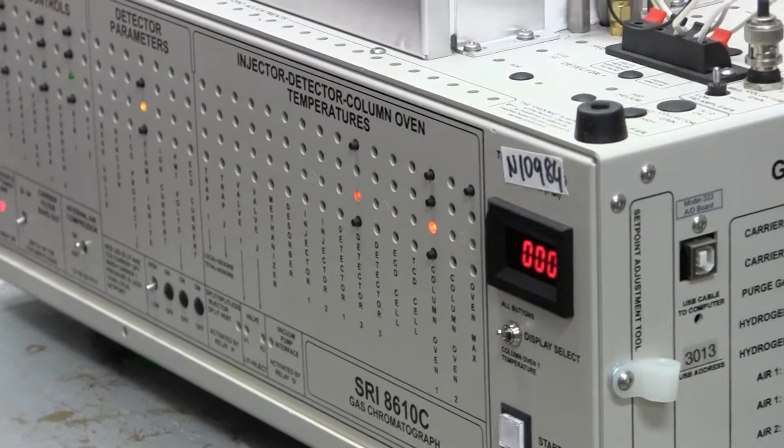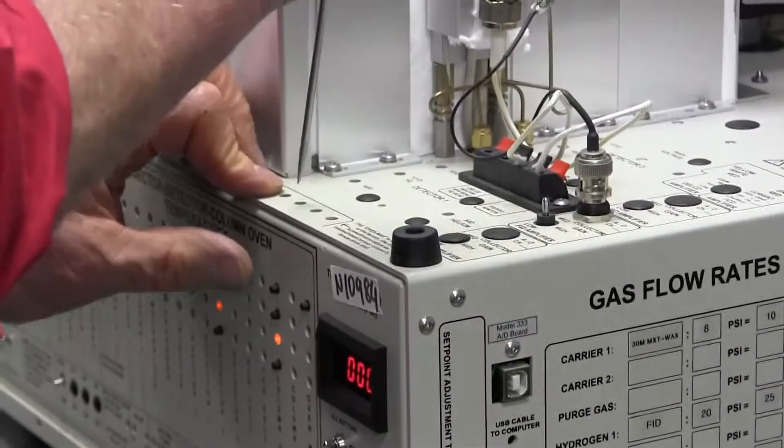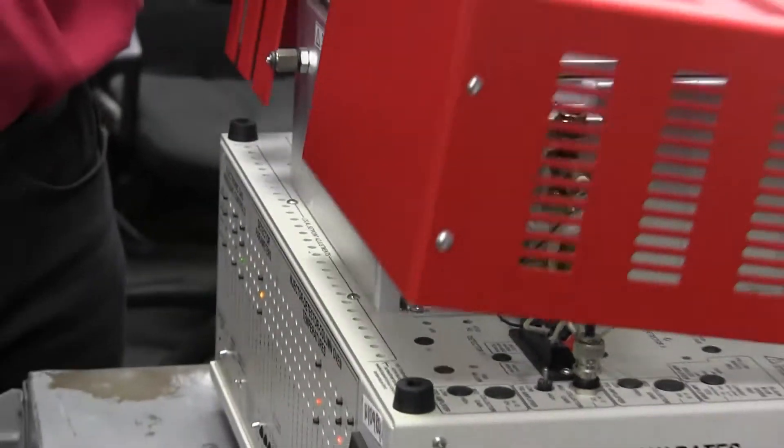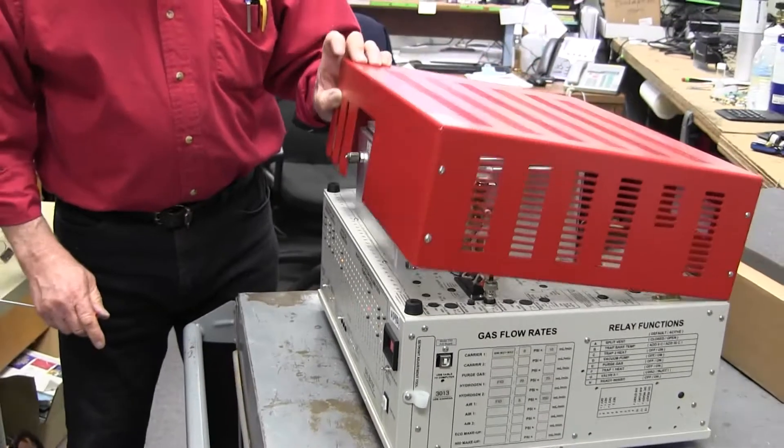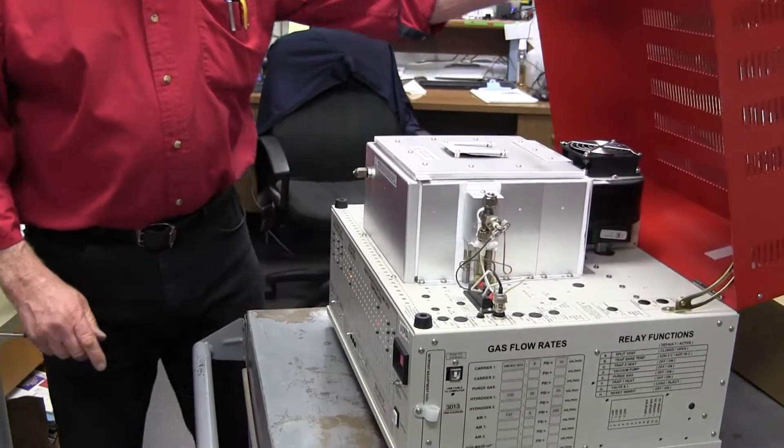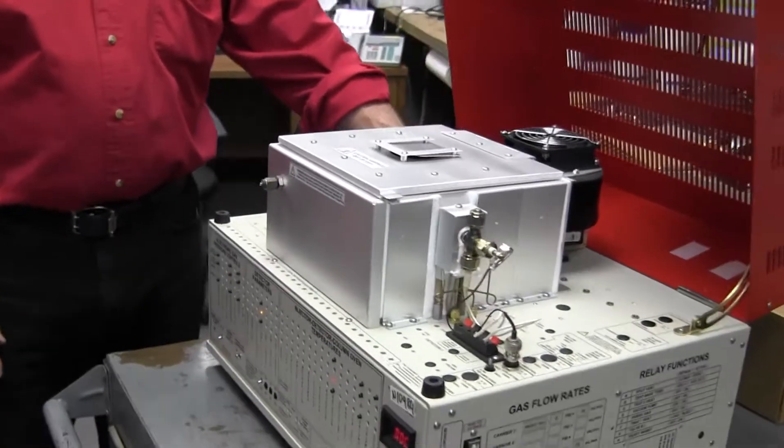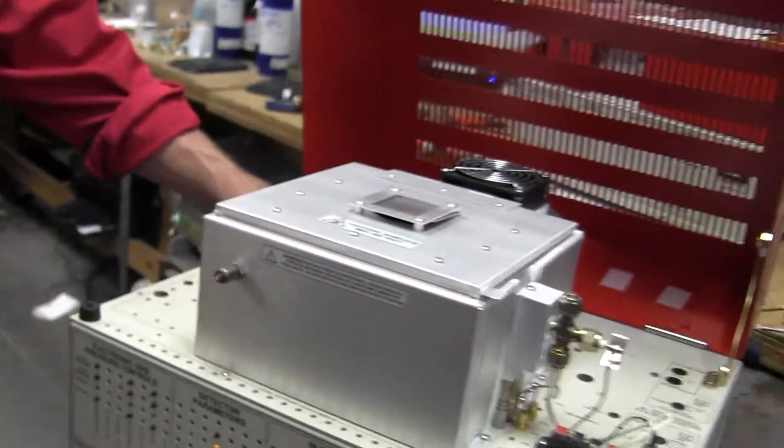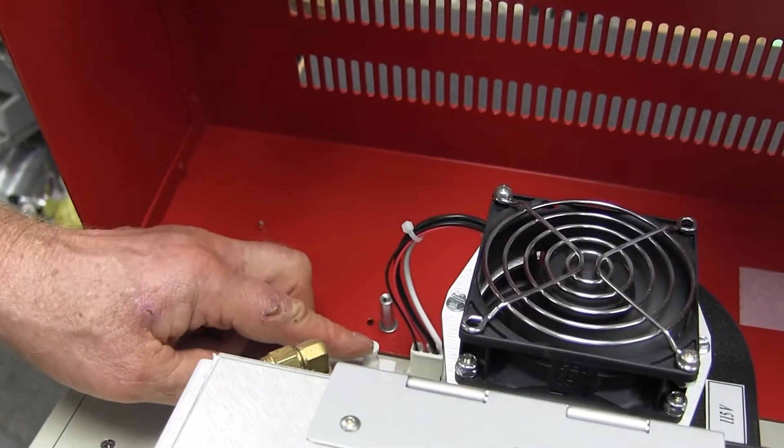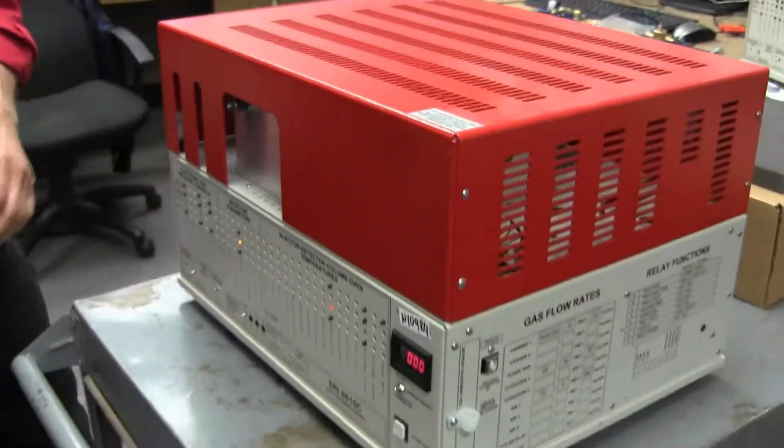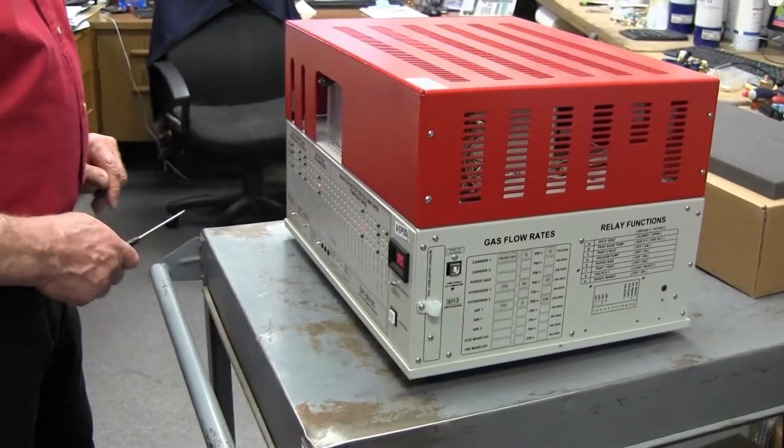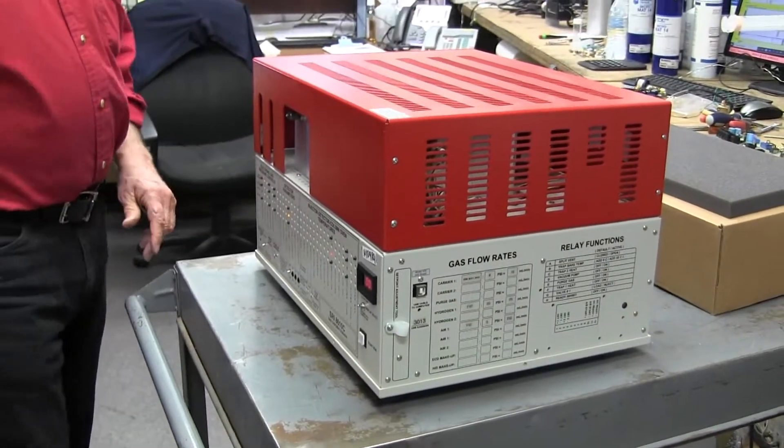by turning off something called a relay, which is a big electromagnetic thing that makes a clunking sound when the lid closes. Do you hear that kind of click sound? You can also actuate that big clunky relay manually by depressing this white plunger in the back. The lid hits the plunger on its way down, and that's when everything starts to heat. And so that's the most common reason why the thermocouple out-of-range alarm might be on.